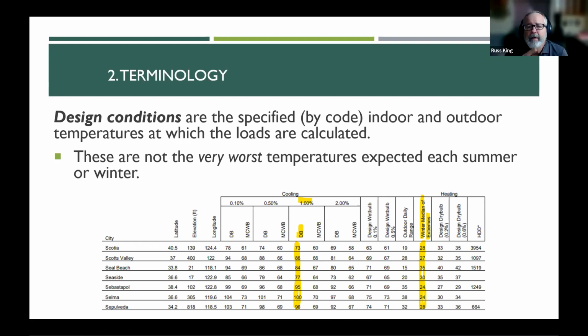And because air conditioners and heat pumps and furnaces only come in certain increments, you're almost by definition going to be slightly oversized, okay? Because they don't make equipment that's exactly the same capacity as your load. There's only certain increments. So you're going to pick the next larger one or the next smaller one. If it's really, really close, it's okay to pick the next smaller one. But even so, there's some slop and there's some safety margin built into the load calcs, okay?